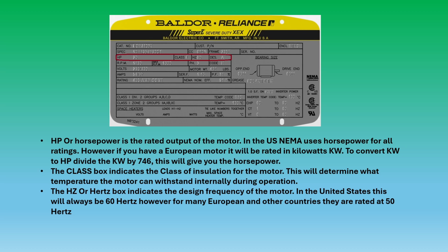HP or horsepower is the rated output of the motor. In the US, NEMA uses horsepower for all ratings. However, if you have a European motor, it will be rated in kilowatts or kW. To convert kilowatts to horsepower, you need to divide the kilowatts by 746. This will give you the horsepower. The class box indicates the class of insulation for the motor. This will determine what temperature the motor can withstand internally during operation.